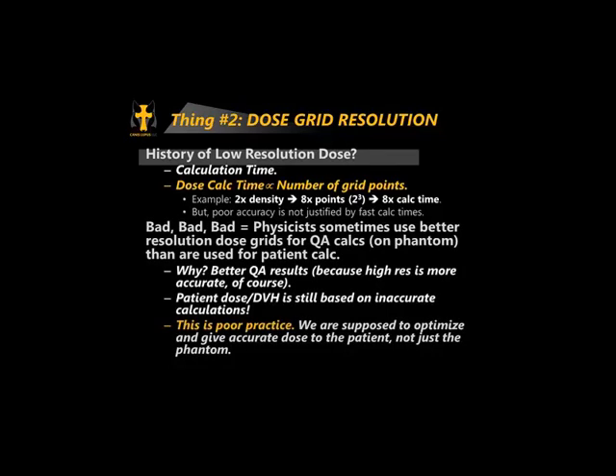A problem that exists out there: a physicist may ask you to do QA calculations at higher resolution because they get better results — because the calculation is more accurate and better matches measurement. But if you're using a higher resolution for QA calcs than for patient plans, that's completely off the rails. That means you realize you need high resolution to get it accurate — you do that for QA calcs, but if you don't do it for patient calcs, you're accepting garbage on your patient calcs. This is a very poor practice.